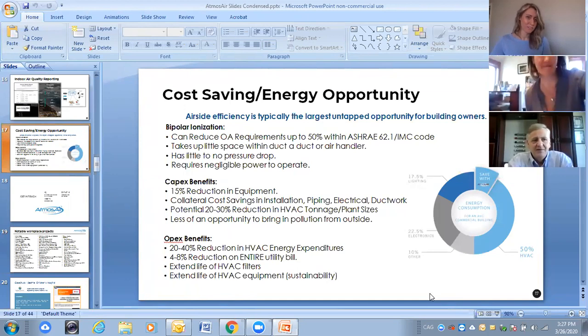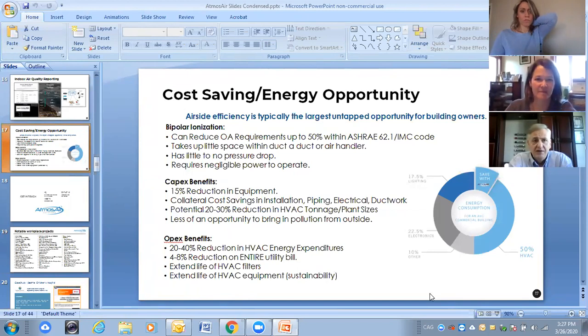What that standard does is say to an engineer, in order to provide good air quality to a building, you need to design around these parameters. One of those parameters is bringing in air from the outside, since in a commercial building you don't really have much of an option to open windows anymore. So you have to mechanically ventilate the space. Now, there's what's called a prescriptive code. I have a certain building and a certain number of occupants, and I need a certain amount of outside air to subscribe to correct ventilation engineering. And it's prescriptive. A gymnasium versus an office building versus an animal boarding kennel have different values: the amount of outside air per person, and outside air per square foot of space you must engineer.